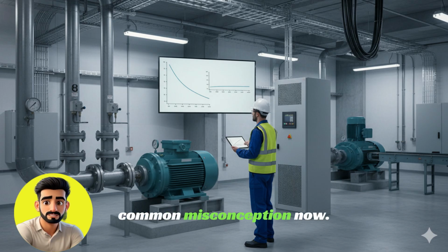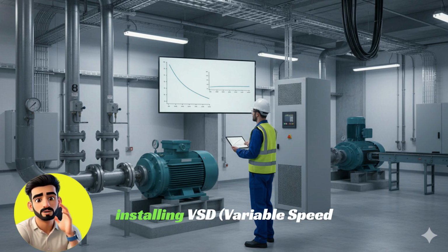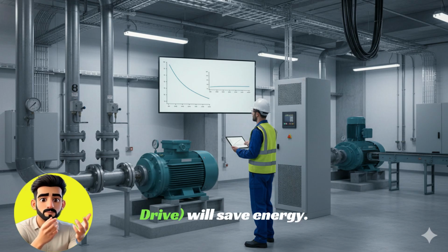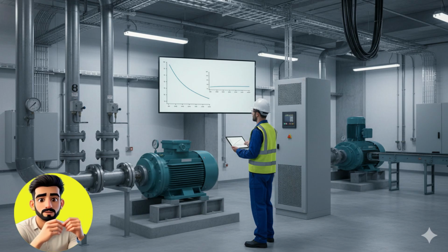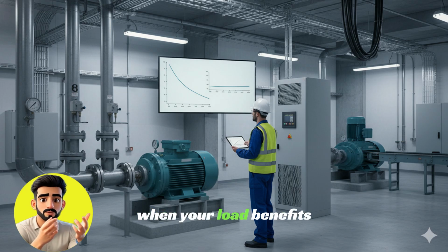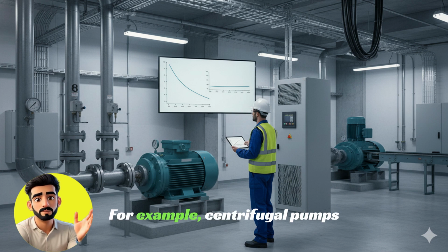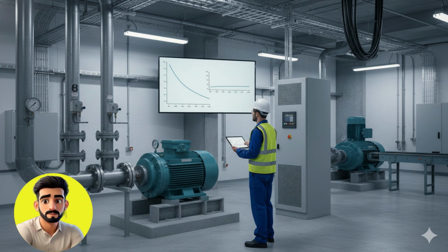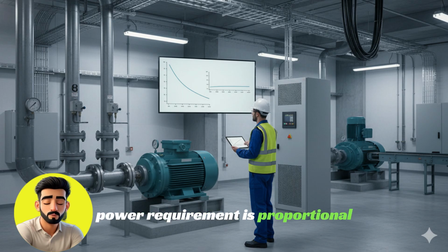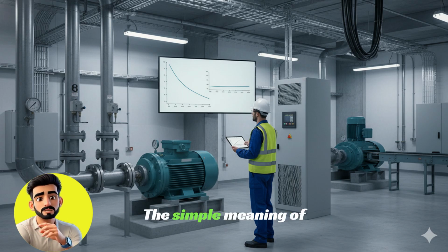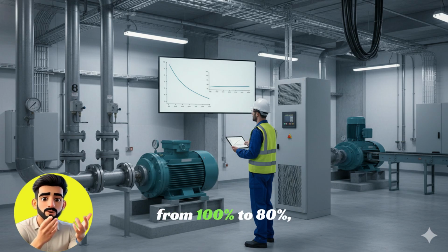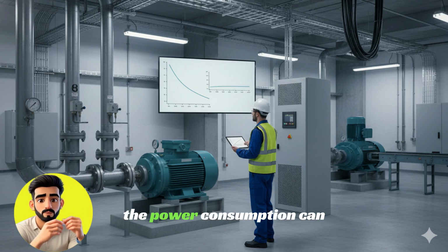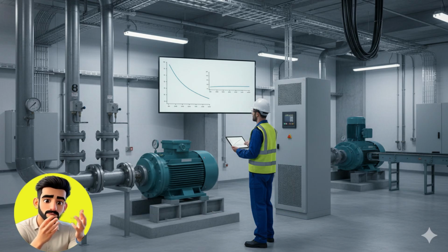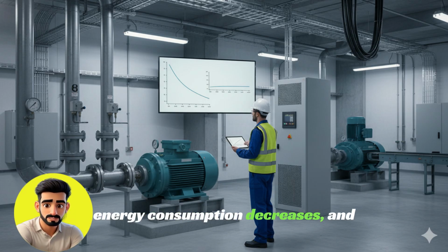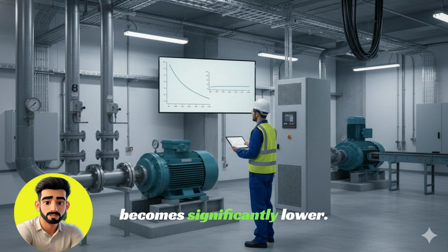Let's clear a very common misconception now. Many people think that installing VSD, variable speed drive, will save energy. But what is the truth? Energy saving occurs only when your load benefits from speed reduction. For example, centrifugal pumps and centrifugal fans. In these loads, the power requirement is proportional to the cube of the speed. The simple meaning of this is that if you reduce the speed from 100% to 80%, the power consumption can be reduced to almost half. Here, VSD becomes a goldmine. The speed is reduced, energy consumption decreases, and the electricity bill also becomes significantly lower.